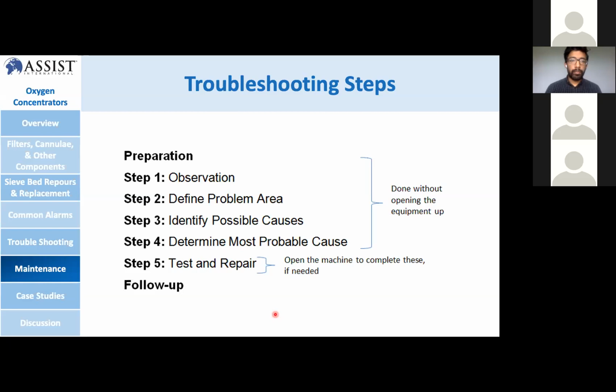And the fourth one is determine most probable cause. So for most probable cause, there are components that are easily breakable, like components that burn out or wear, like fuses and switches, which are highly likely to fail. Components that generate heat, like transformers and coiled equipment, and loose connections are very highly likely to fail, and so is defective wiring. So all this, from the first to the fourth step, is done without opening the equipment. It's just to analyze it.